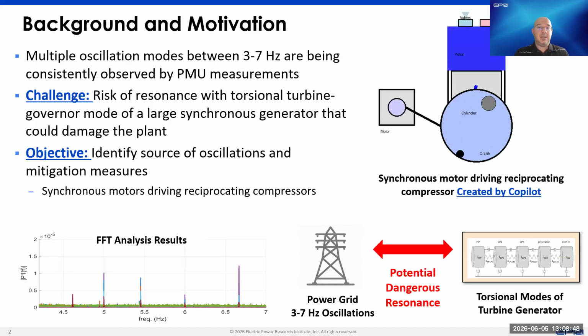So that's the motivation. As a spoiler alert, you saw from the title also that after the analysis, we found and validated that the source of those oscillations were synchronous motors driving reciprocating compressors. These oscillations were caused by industrial load plants within specific areas that use those synchronous motors with reciprocating compressors, and because of their cyclic loading pattern, they are introducing those forced oscillations into the system. We'll discuss more details in the next slides.